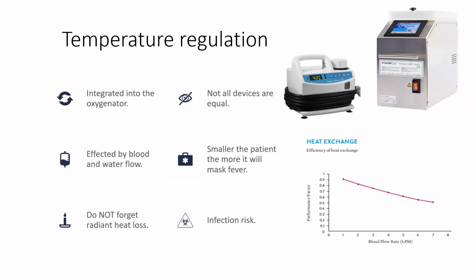Temperature regulation, I touched on this very briefly as far as heating and cooling patients through the oxygenator itself. All oxygenators except for the Spectrum oxygenator that's out on the market, it's integrated into the oxygenator.